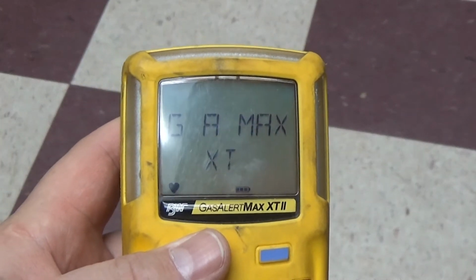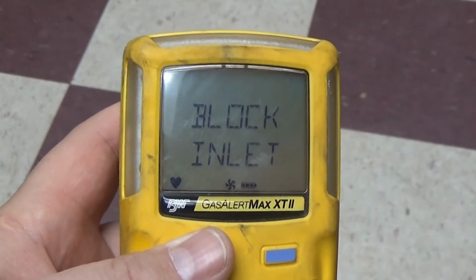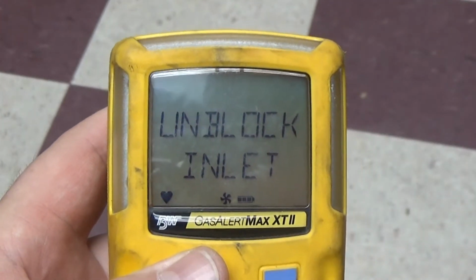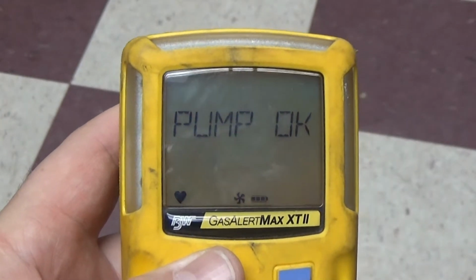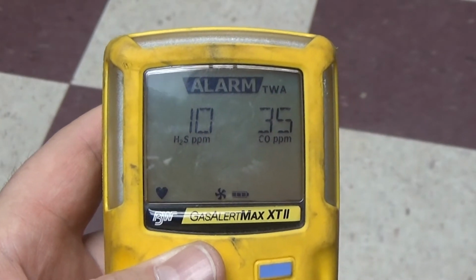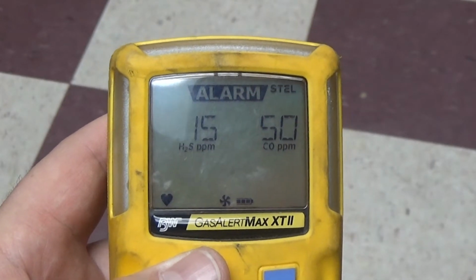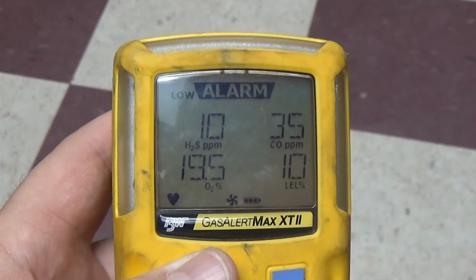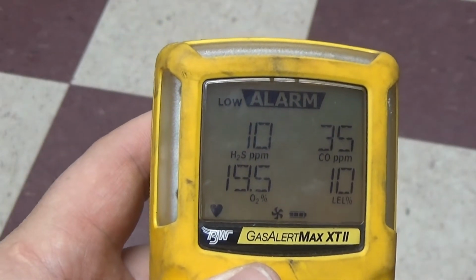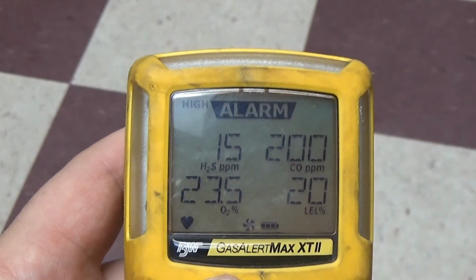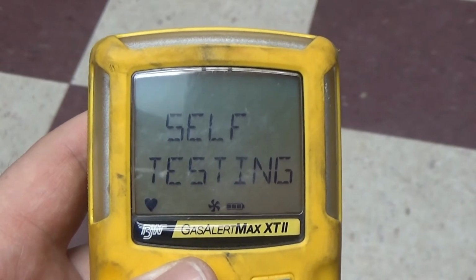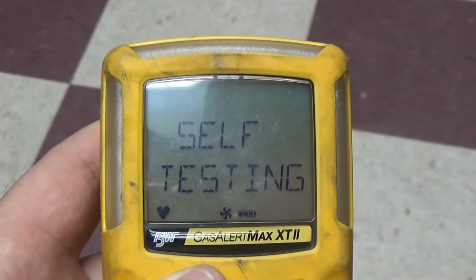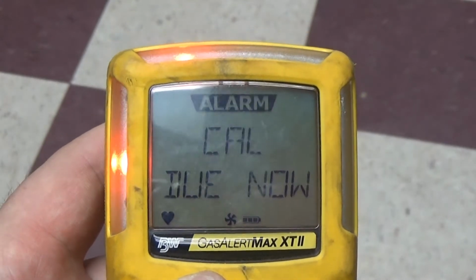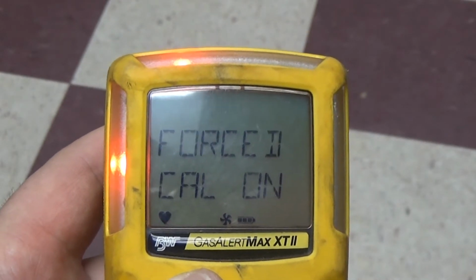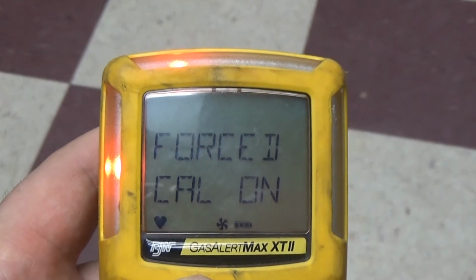We're now going to move on to calibration of the meter. It's the same process, so when you start up the meter, you block your inlet, let it start up, and if your meter needs to be calibrated, it's the first alarm that it's going to give you. Let it go all the way through the process and start up. After it's completely started up, it's going to tell you that the force calibration is on.